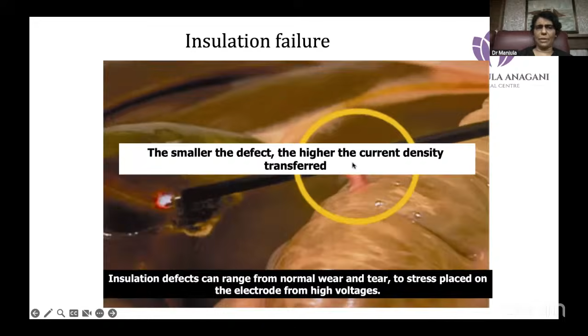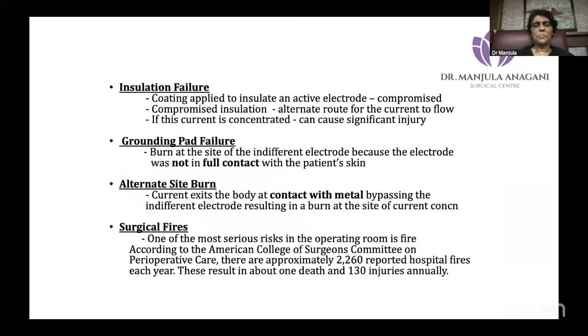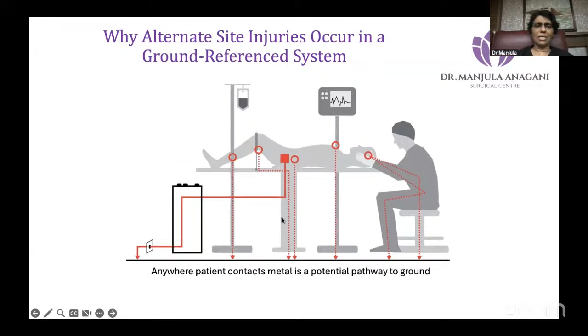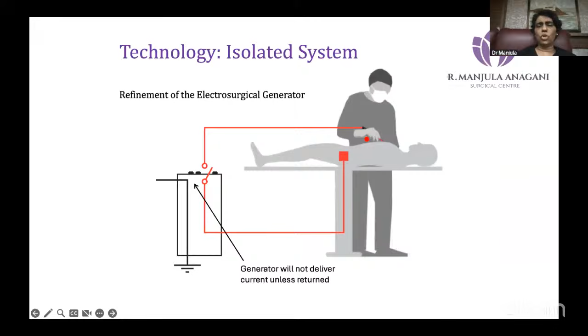Insulation failure, I told you there's a hole through which it can happen. The smaller the defect, the higher the current density transfer. Whenever they contact the metal, there are surgical fires. I have not seen a surgical fire except in Grey's Anatomy. Previously, when alternate site injuries used to happen, it was because of the earthing, that is the ground reference system, which used to be there. But now we have an isolated system where, until the path comes back to the generator, it does not get activated. So do not compromise with the generator system.